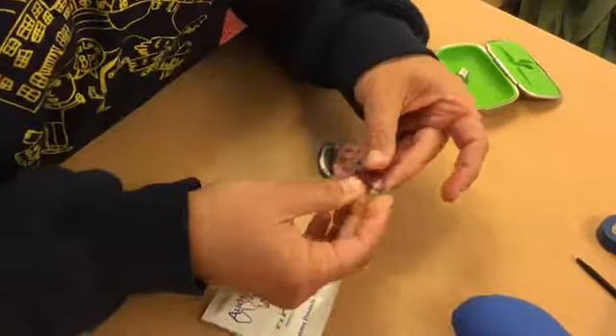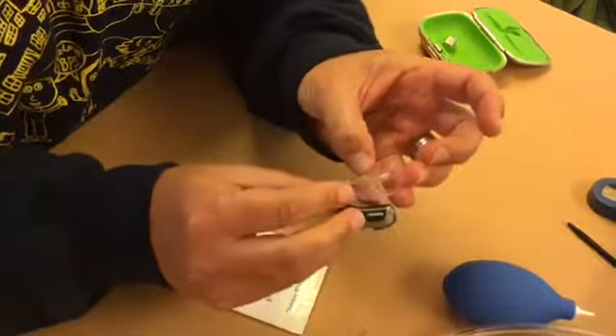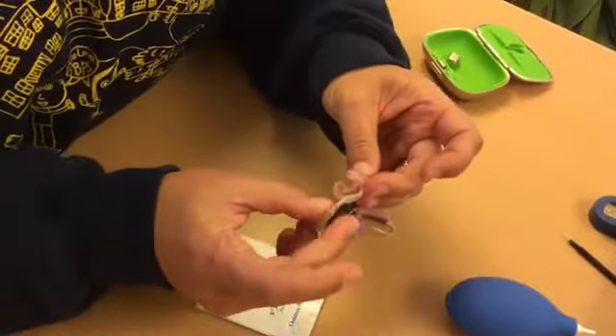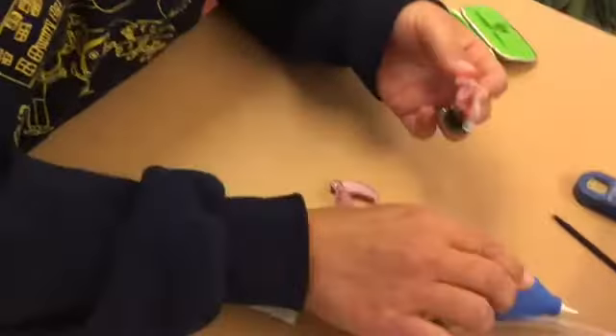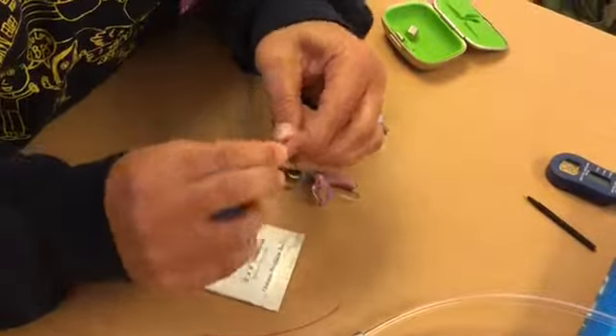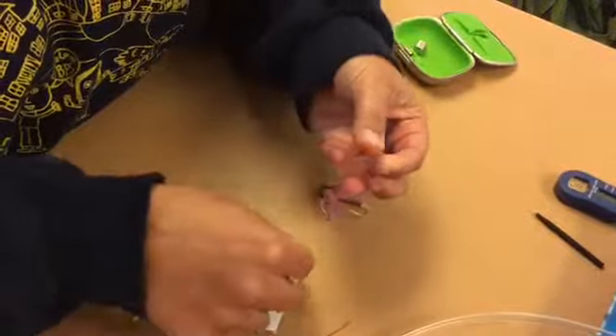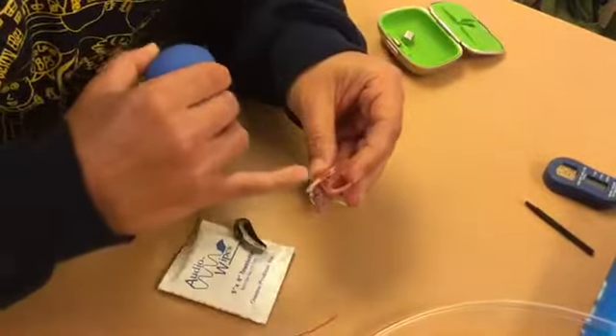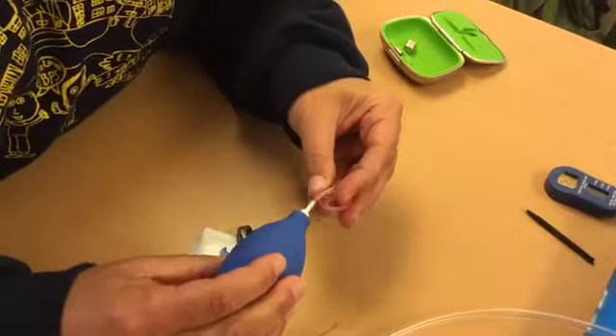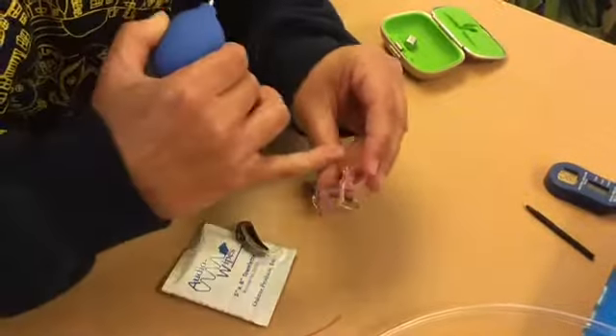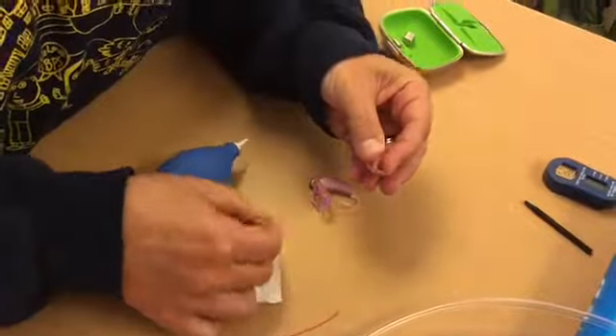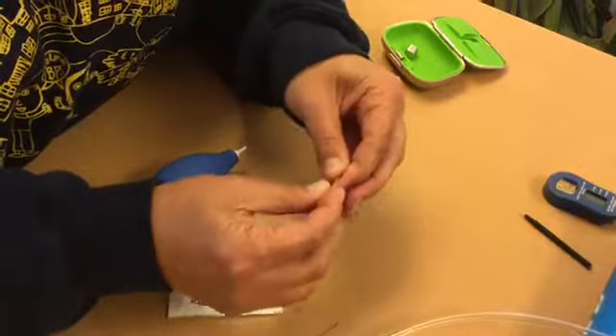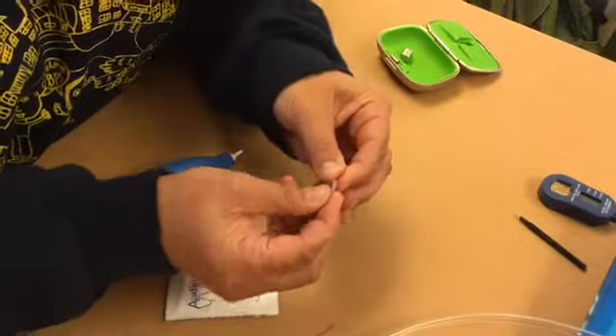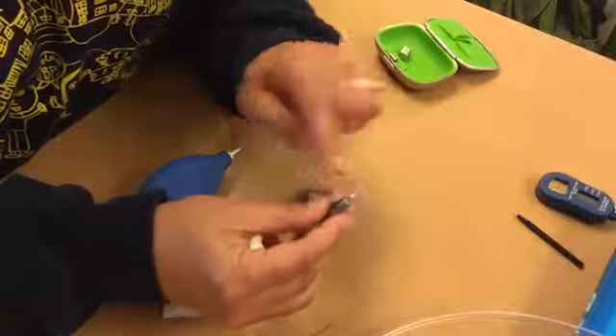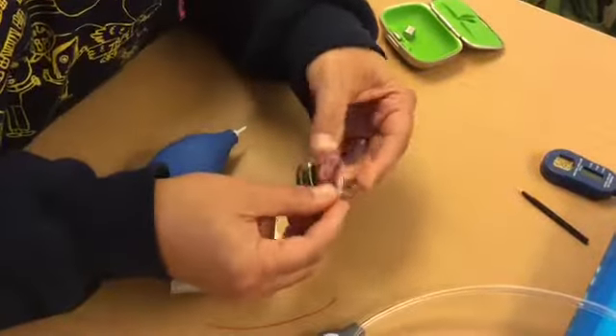It's threaded. And when I look at the tube for the hearing aid, it's a little thicker. So this won't have a thread, but you'll be able to see, and you're looking for any moisture. If you had any moisture in the tube, what you want to do is this part can be removed. Most of the time you're not going to see anything, but it's good to check. You take this off and you can actually use this. It blows air right in until that moisture dissipates in the tube. And then you can just sort of twist, put this part right on. This is meant to be removed and put back on. We don't remove it from here. So that's how you check that tube.